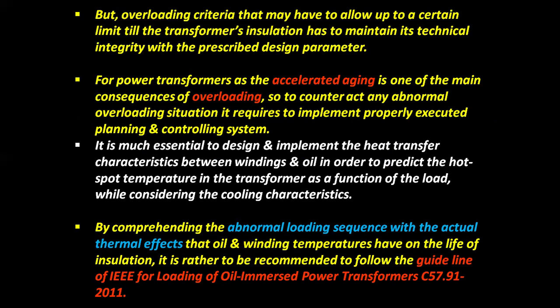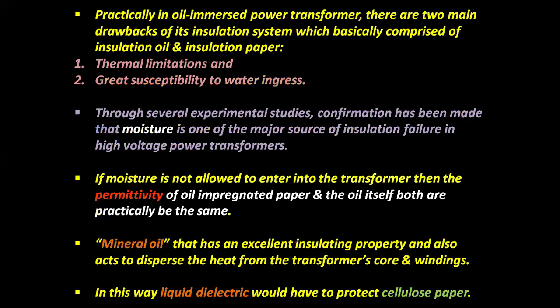By comprehending the abnormal loading sequence with the actual thermal effects that oil and winding temperatures have on the life of insulation, it is recommended to follow the guideline of IEEE for loading of oil immersed power transformers, C57.91-2011.